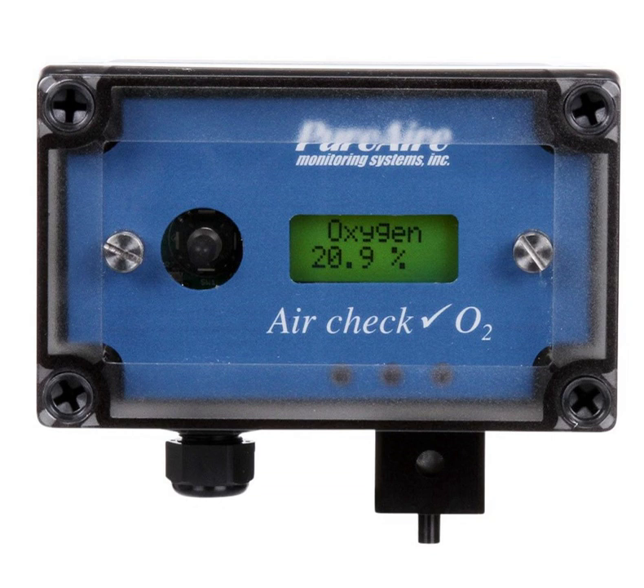All gas detectors must be calibrated on a schedule. Of the two form factors of gas detectors, portables must be calibrated more frequently due to the regular changes in environment they experience. A typical calibration schedule for a fixed system may be quarterly, biannually or even annually with more robust units. A typical calibration schedule for a portable gas detector is a daily bump test accompanied by a monthly calibration. Almost every portable gas detector requires a specific calibration gas which is available from the manufacturer. In the US, the Occupational Safety and Health Administration may set minimum standards for periodic recalibration.